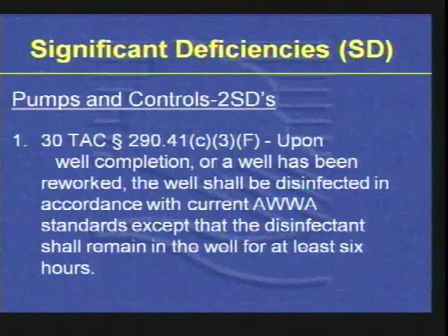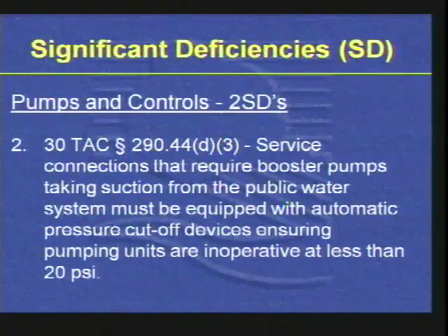The second significant deficiency under pumps is 290.44(d)(3). Service connections that require booster pumps taking suction from the public water system must be equipped with automatic pressure cutoff devices, ensuring pumping units are inoperative at less than 20 psi.